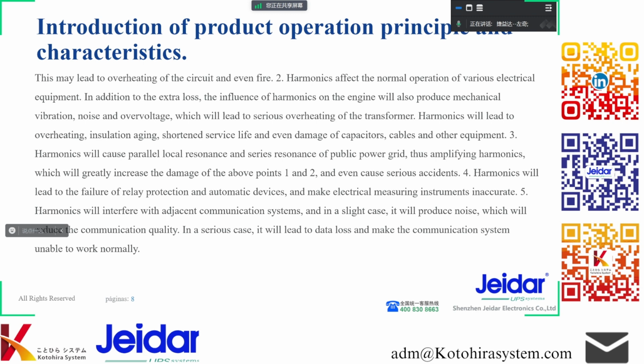Harmonics will lead to overheating, insulation aging, shortened service life, and even damage of capacitors, cables, and other equipment. Harmonics will cause parallel local resonance and series resonance of the public power grid, thus amplifying harmonics, which will greatly increase the damage of the above points 1 and 2, and even cause serious accidents.